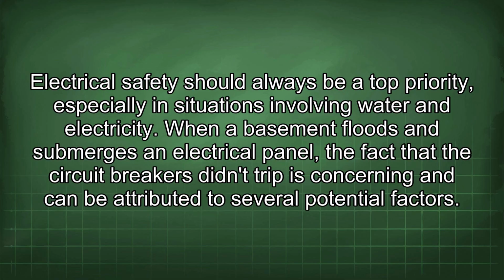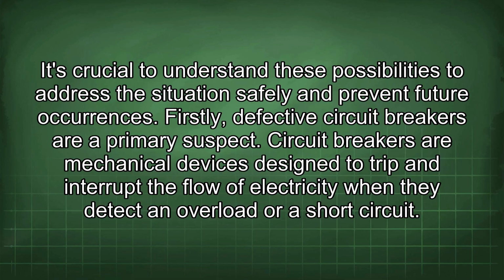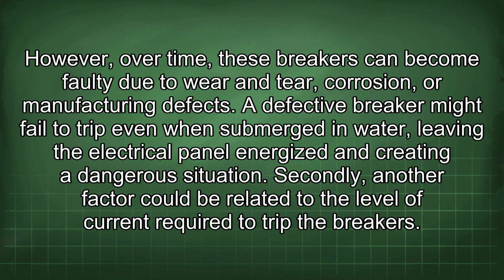When a basement floods and submerges an electrical panel, the fact that the circuit breakers didn't trip is concerning and can be attributed to several potential factors. It's crucial to understand these possibilities to address the situation safely and prevent future occurrences. Firstly, defective circuit breakers are a primary suspect. Circuit breakers are mechanical devices designed to trip and interrupt the flow of electricity when they detect an overload or a short circuit. However, over time, these breakers can become faulty due to wear and tear, corrosion, or manufacturing defects.